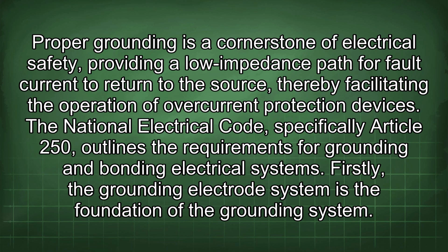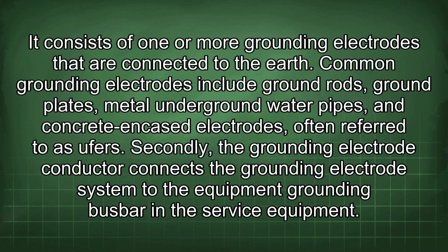Firstly, the grounding electrode system is the foundation of the grounding system. It consists of one or more grounding electrodes that are connected to the earth. Common grounding electrodes include ground rods, ground plates, metal underground water pipes, and concrete encased electrodes, often referred to as UFERs.